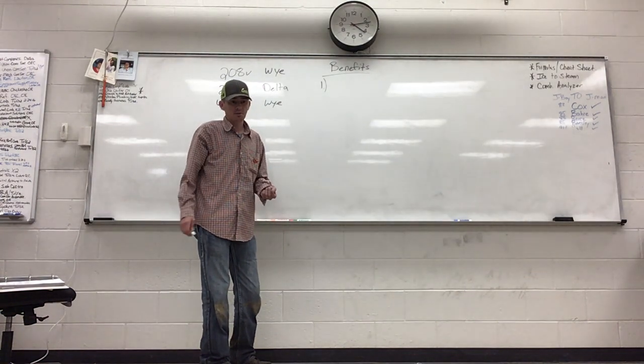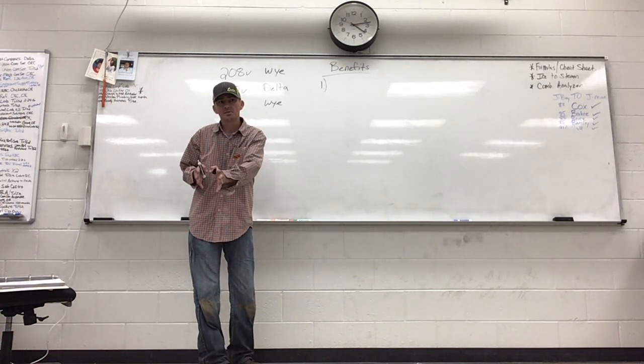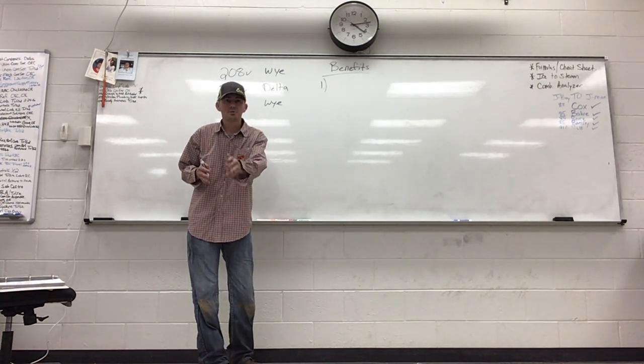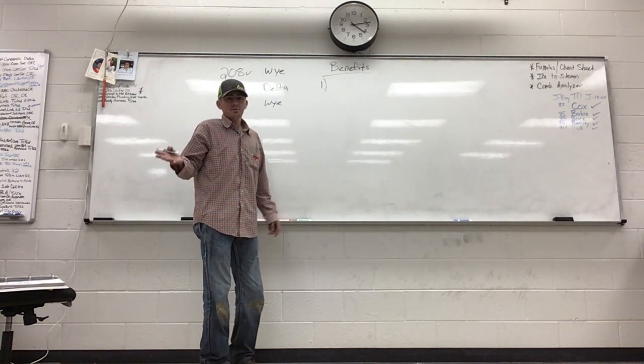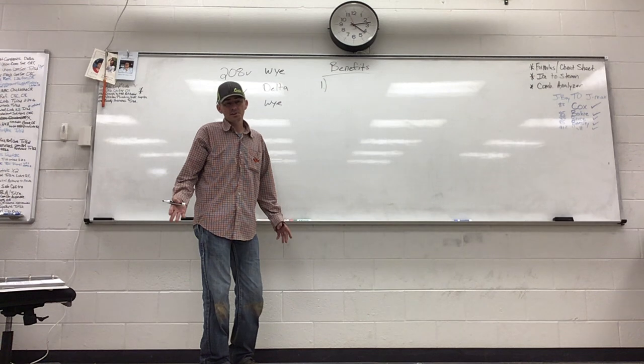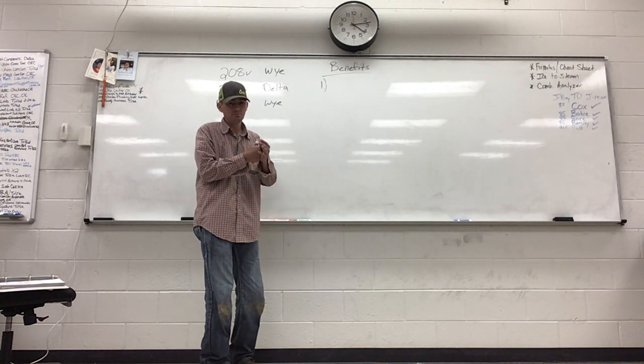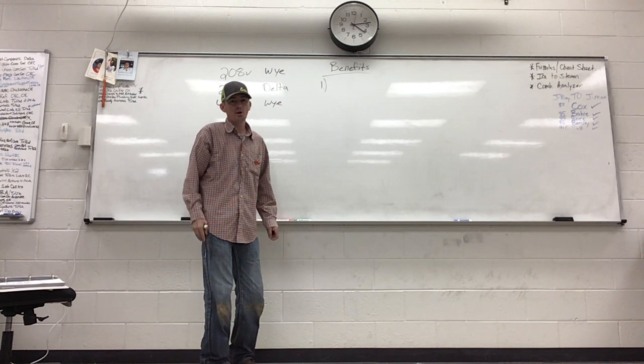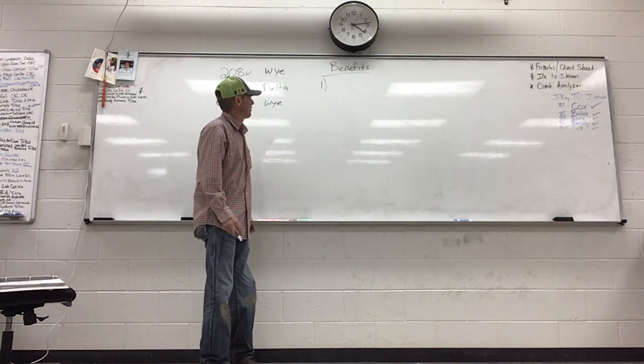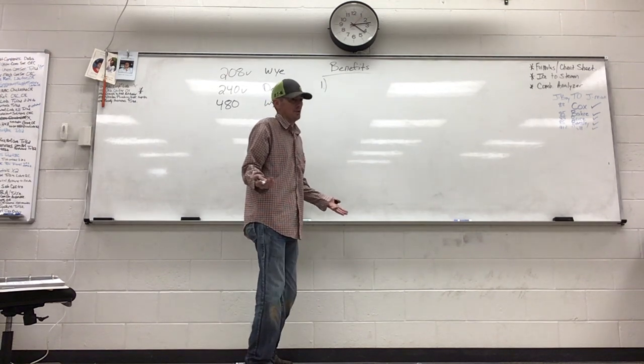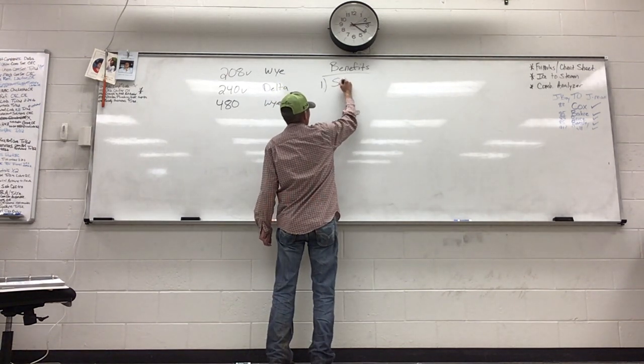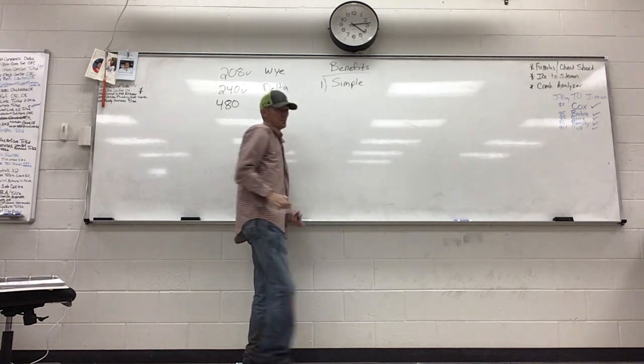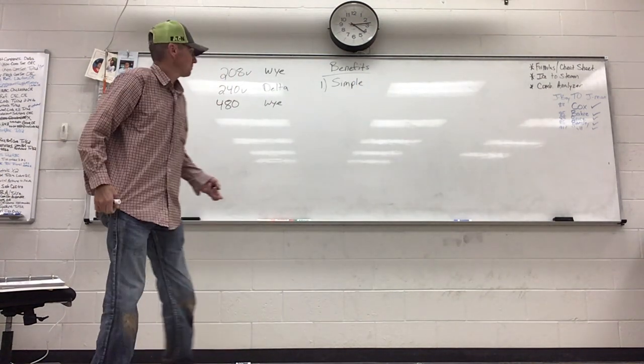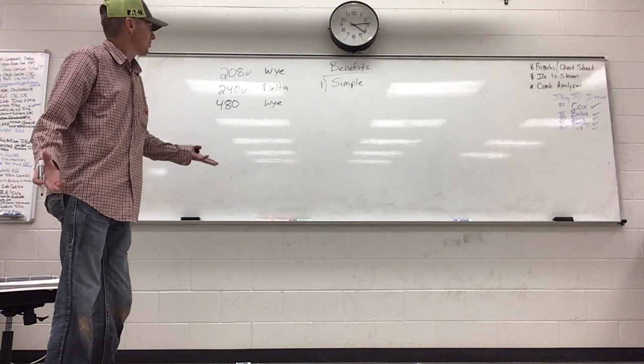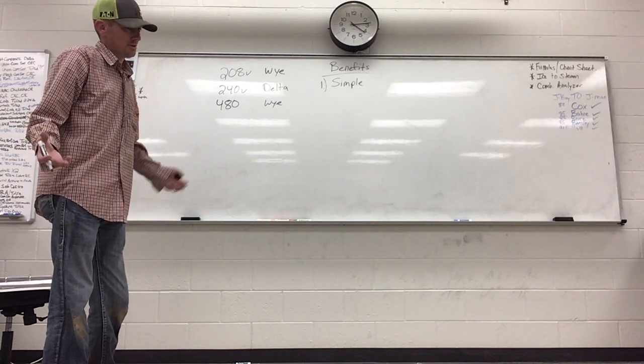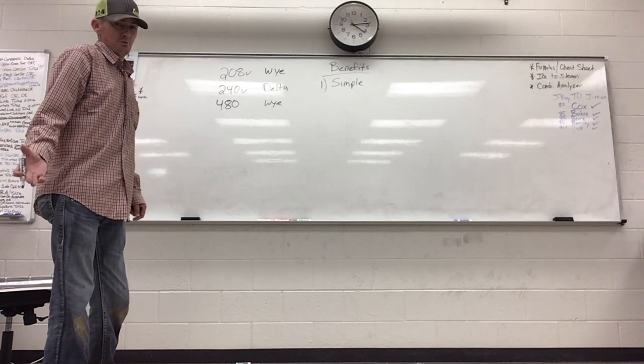I've already said it twice, but the capacitor start, capacitor run has a run winding, start winding, potential relay, start capacitor, run capacitor, and on. Whereas the three-phase motor, if we're starting it across the line, has a three-pole contactor, boom, and three sets of windings, and that's it. So probably the first benefit is the simplicity of it. Three-phase power is simple. We're going to get into part winding start and Y delta start and stuff. It gets a little more complicated, but compared to a single phase capacitor start, capacitor run with potential relay and all that good stuff, it's super simple.